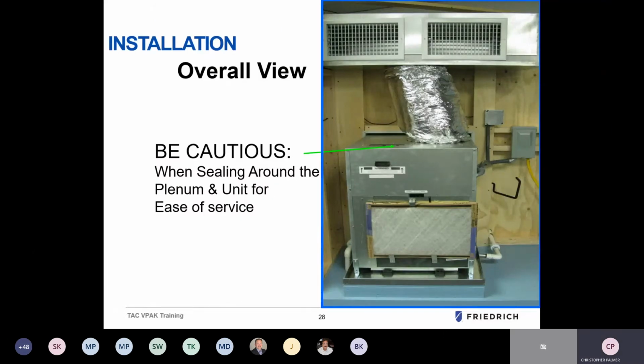And then one here on the overall view of the unit installed, when you're sealing the ductwork around the top of the plenum or top of the takeoff of the unit, make sure that you're careful with any kind of duct sealant, mastic, screws, tape, whatever, because there are access panel screws that can be difficult to get to in the event that you need to service the top of the unit. From being in the field, I know that we can get a little aggressive with the mud and slap it on all the way around the top here, and it makes it trouble for the guy coming behind you to service the unit or get the unit in and out.